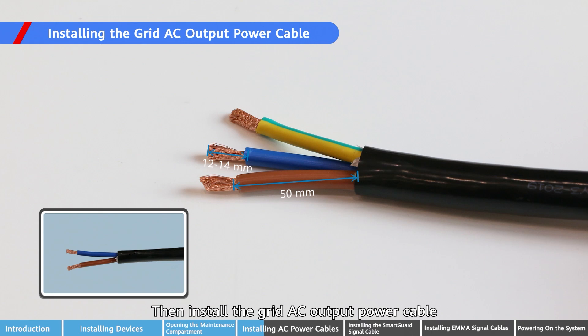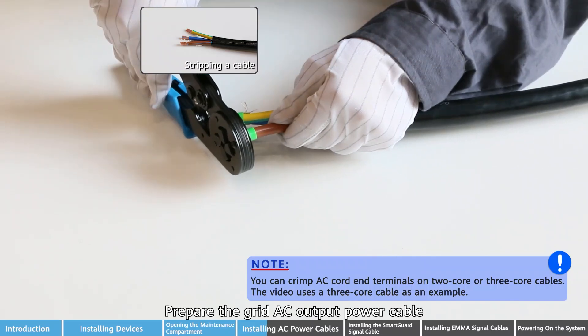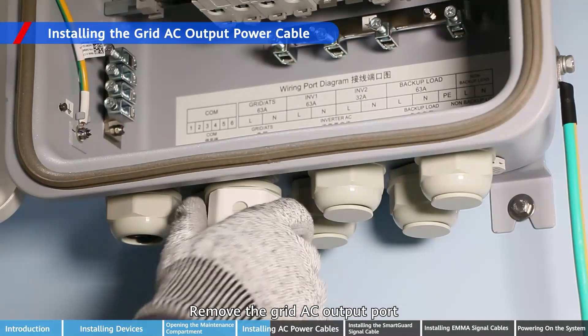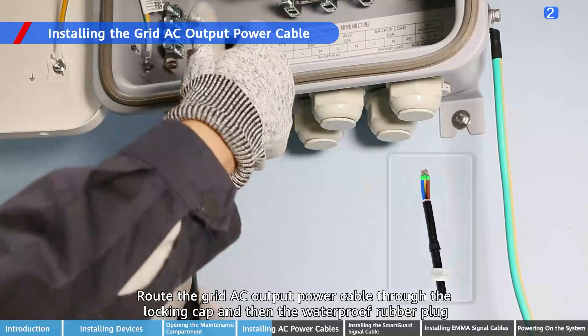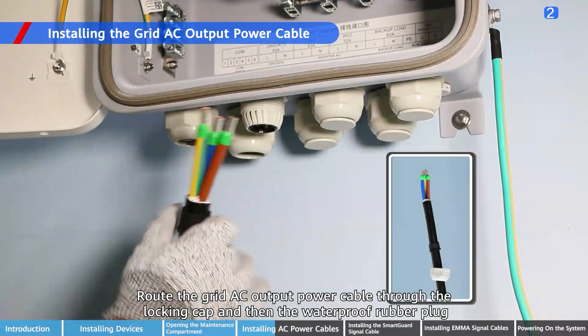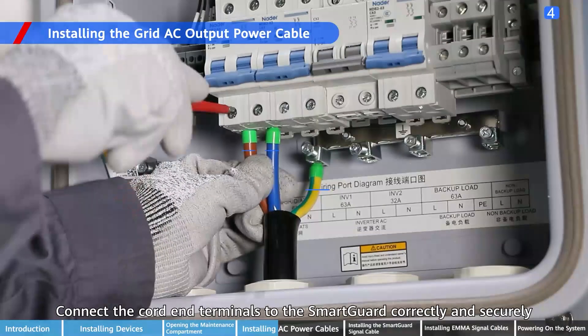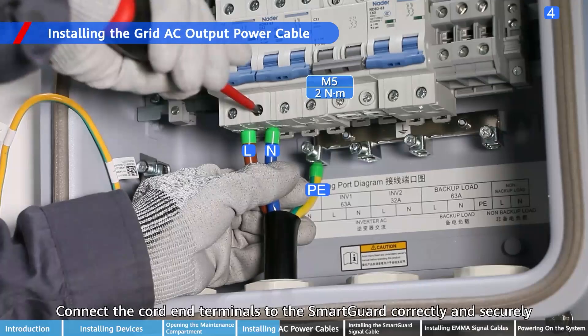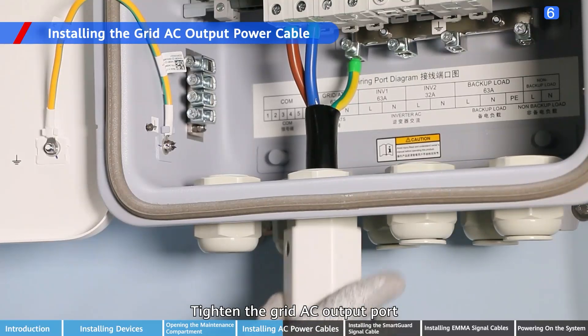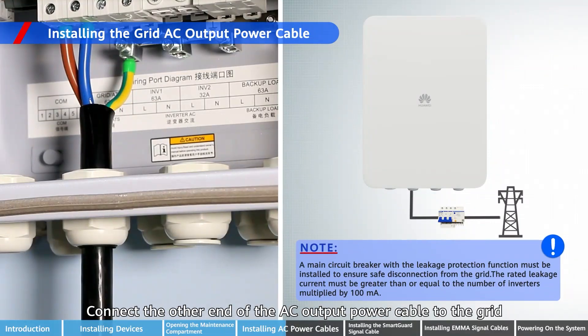Install the grid AC output power cable. Remove the grid AC output port. Route the grid AC output power cable through the locking cap and then the waterproof rubber plug. Connect the cord end terminals to the SmartGuard correctly and securely. Tighten the grid AC output port. Connect the other end of the AC output power cable to the grid.